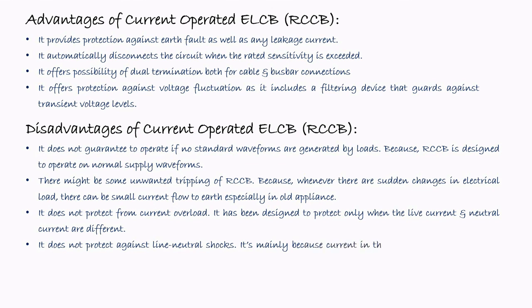It does not protect against line to neutral shocks. It is mainly because the current in them is balanced. The current gets balanced as both the terminals are held together. That's why it will not work in this particular case.